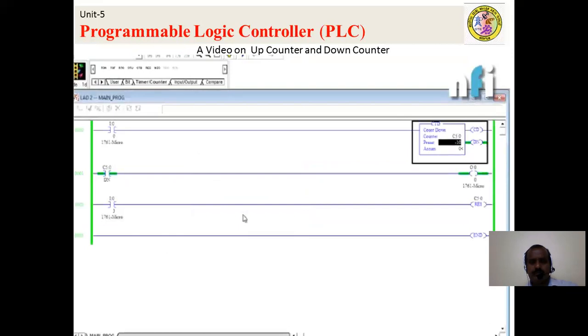So right now it is on because 0 is greater than -10. It is going to minus. So as soon as it goes -11, output will be off because accumulator is less than this preset. So when I reset this accumulator again, output will be on. Accumulator is more. Now when I press it again up to 11, accumulator is less than preset, so output is off. So that's countdown. It will always decrement the accumulator, and count up will always increment the accumulator.